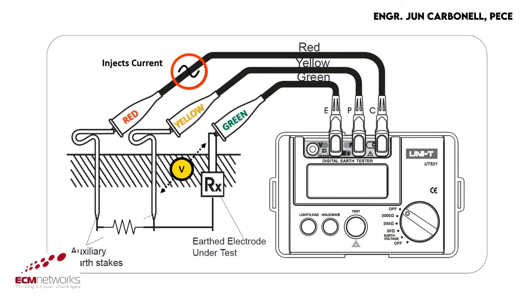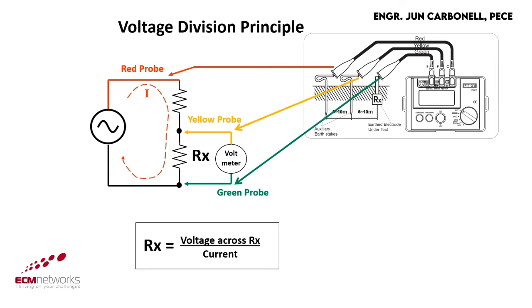In this configuration, the C port will inject 50 volts AC to the ground, flowing from the red test lead to the ground. Current will now flow from the red probe to yellow probe resistance and the yellow probe to green probe resistance, which is the ground rod resistance. The yellow port and green port will act like a voltmeter which measures the voltage across this point. Inside UT521, it will divide the voltage measured by the AC current it generated, and resistance can now be computed.